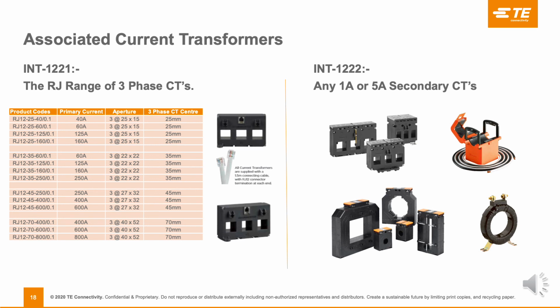If you've got any 1 amp or 5 amp CTs, split core, 3-phase, molded case, ring type CTs, any 1 amp or 5 amp CT will work with the Integra 1222 functionality. When you've got both of them in the panel, they will look and function exactly the same.